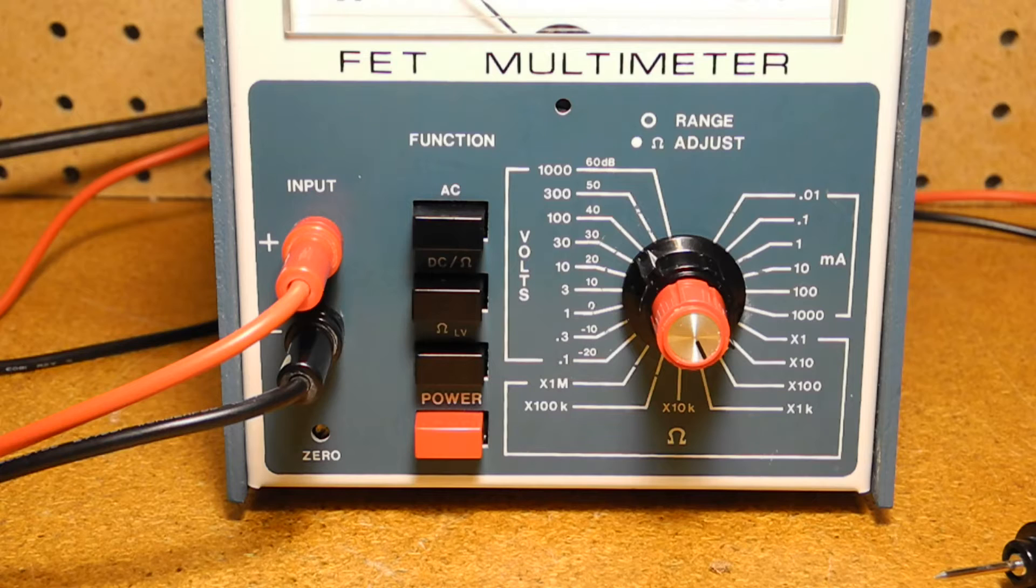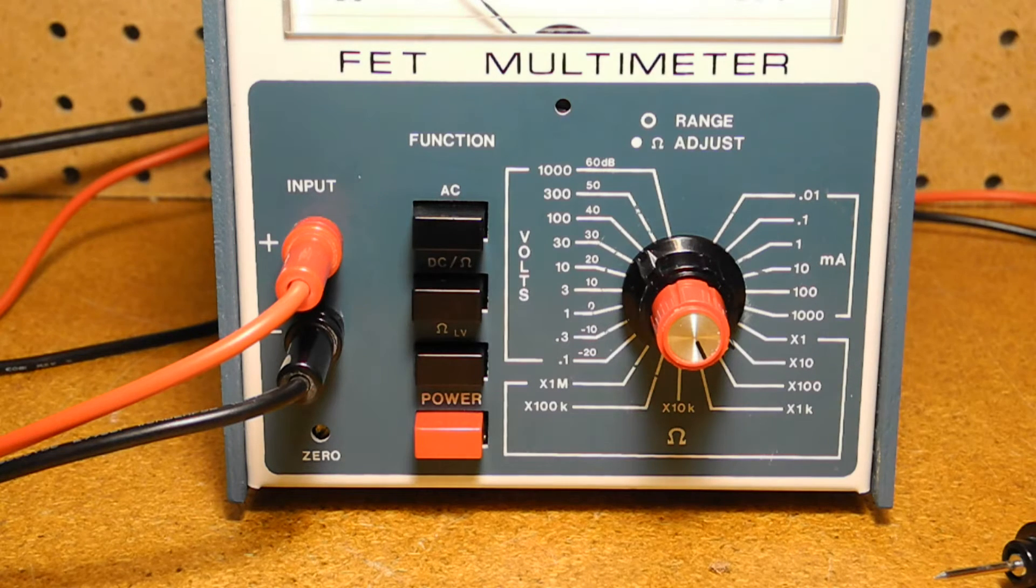DC volts can be measured on nine ranges, 0 to 0.1, 0.3, 1, 3, 10, 30, 100, 300, and 1000 volts DC full-scale. Input resistance is 10 megaohms and is spec'd at plus or minus 2% accuracy.